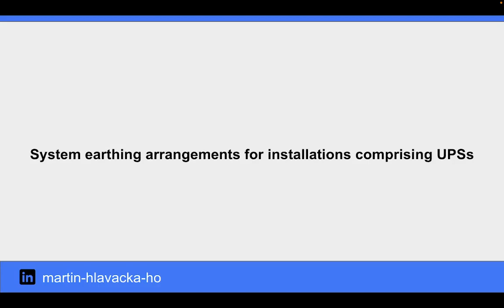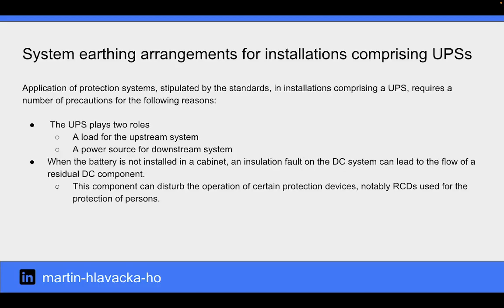System earthing arrangements for installations comprising UPSs. Application of protection systems stipulated by the standards in installations comprising a UPS requires many precautions, as the UPS plays two roles: a load for the upstream system and a power source for the downstream system. When the battery is not installed in a cabinet, an insulation fault on the DC system can lead to the flow of a residual DC component. This component can disturb the operation of certain protective devices, notably RCDs used for the protection of people.